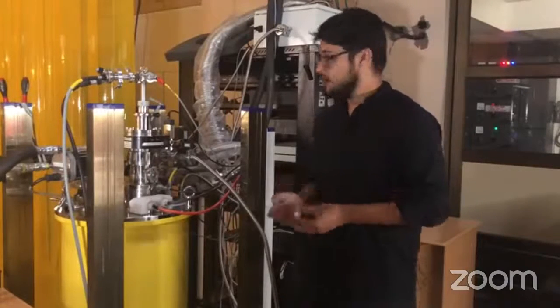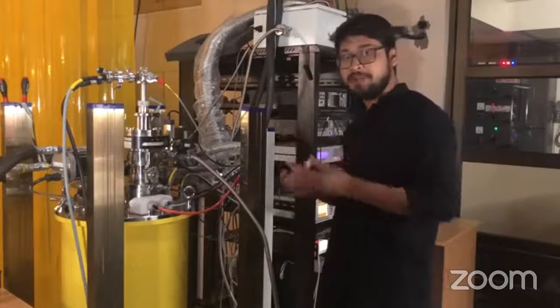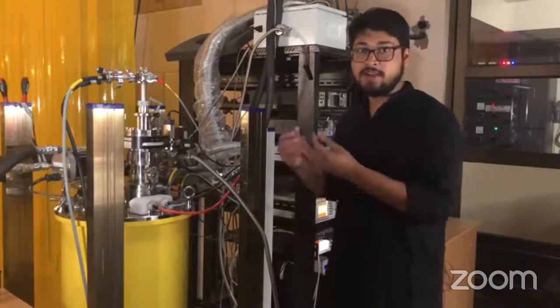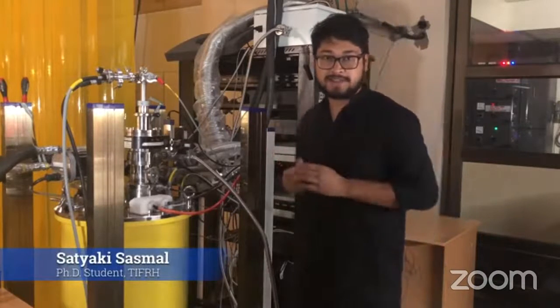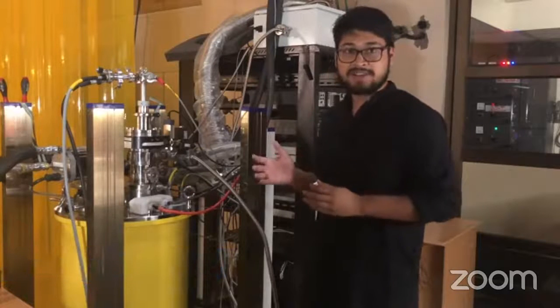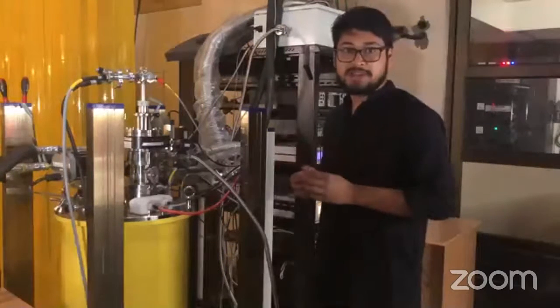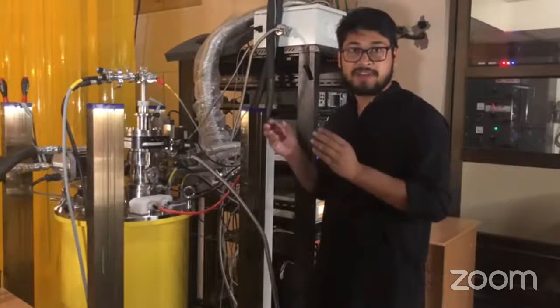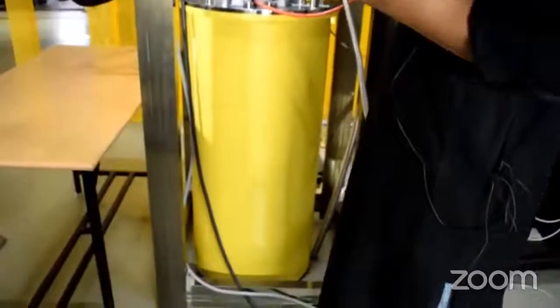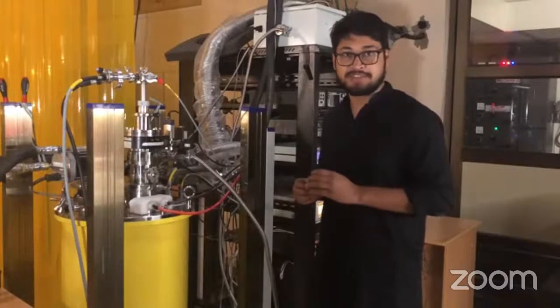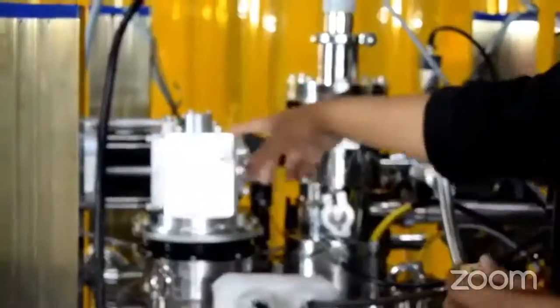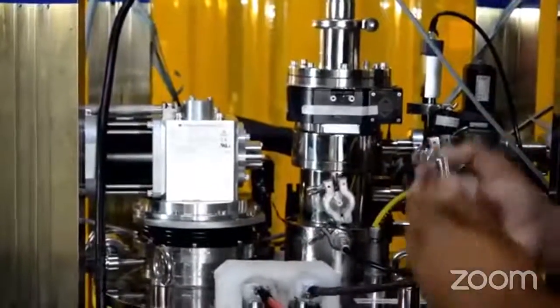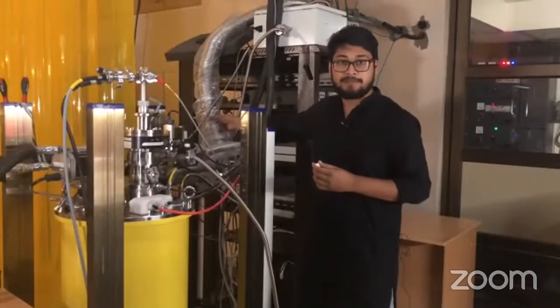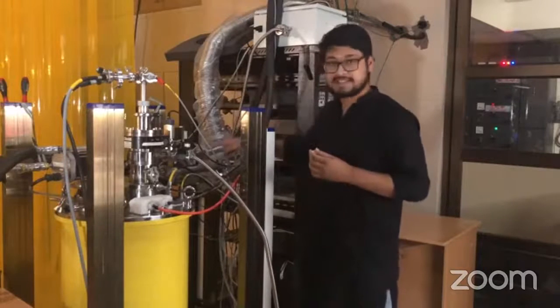After preparing the samples, we use this instrument to measure different electronic properties of those samples, like electron density, hole density, resistivity, mobility, conductivity, this kind of thing. So before measuring any of these properties, first we need to remove all the heat from the sample to remove any thermal noise coming from the vibration of atoms. So this chamber is basically a refrigerator which cools down the sample to very low temperature, almost close to absolute zero. So this is a compressor that repeatedly compresses and expands helium gas, and doing this repeatedly, it cools down the sample. So if you see this thick pipeline, helium gas comes to this line and goes away.